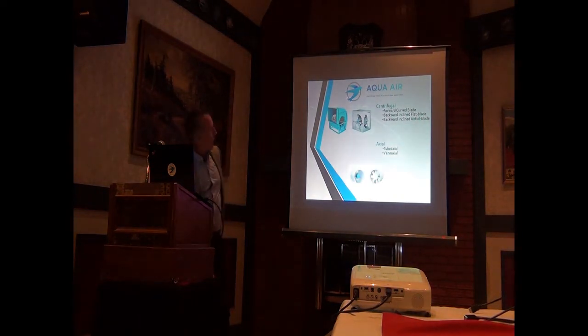When we talk about fans in HVAC, the two main types of fans are centrifugal and axial. In the centrifugal, you have forward curved blade fans, backward inclined flat blade, and backward inclined airfoil blade. If you look at the pictures, this is your standard housing, that would be a forward curved DWDI fan. You'd have this mounted on a base with a motor and pulley to drive it. This is a plenum fan. You'd also probably have it mounted on an isolation base, with the motor and pulley driving it. Axial fans, you have the tube axial and the vane axial.